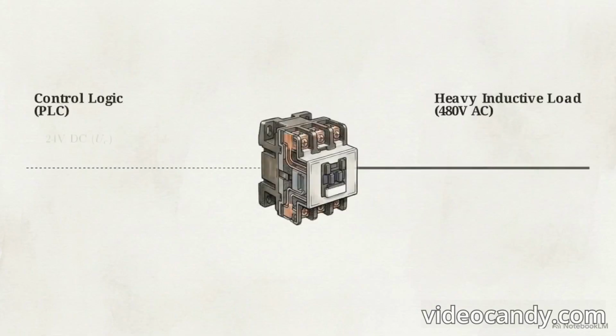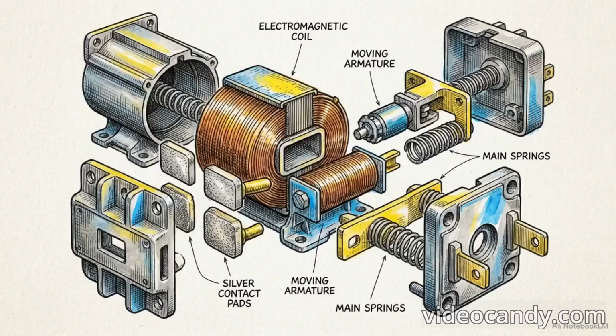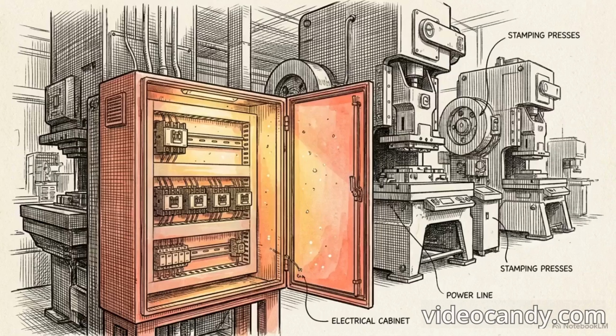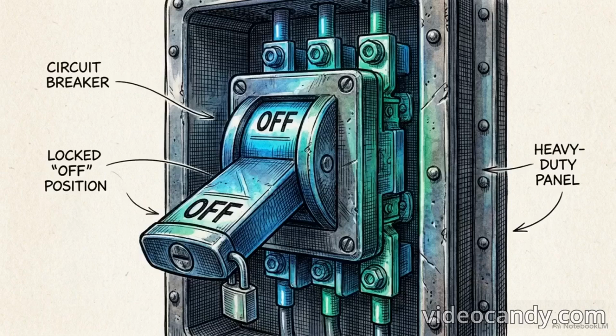It acts as the foundational electromechanical interface, translating the delicate digital commands of a PLC into the physical connection of heavy inductive loads. Inside the housing, the contactor is an engineered node designed to survive the thermal and mechanical shocks of high-frequency switching. It must maintain its structural integrity while operating in hostile electrical environments for millions of cycles.